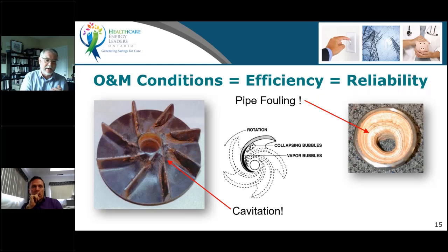And as those bubbles arrive at the impeller after coming in the inlet, they in fact then collapse back to water, and that collapsing causes an erosion of the impeller. We call that cavitation. And this is purely a function of the incorrect operating condition, what we call not enough net positive suction head. And as the temperature of the water rises, you can imagine its propensity to flash to steam or to vapor actually increases. So you need more net positive suction head on a warm water system than a cold water system. Ultimately, the operating conditions can make a huge difference, and that impeller will not behave like the original pump curve would predict. So checking your pumps to see where they're operating is going to be critical.